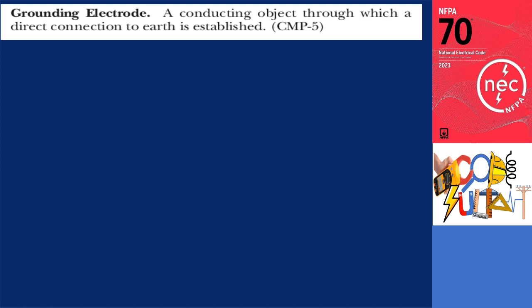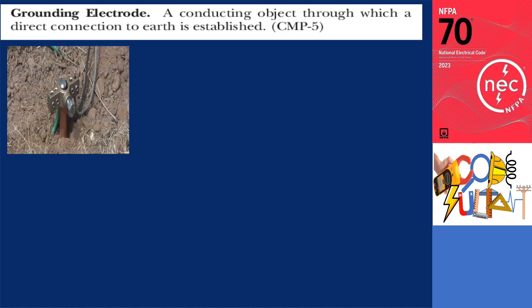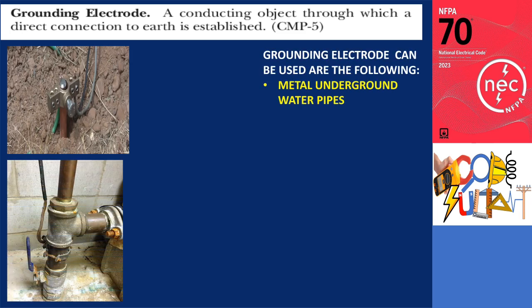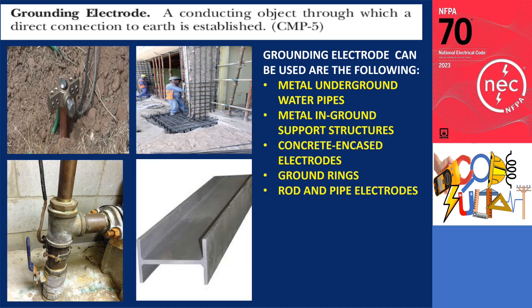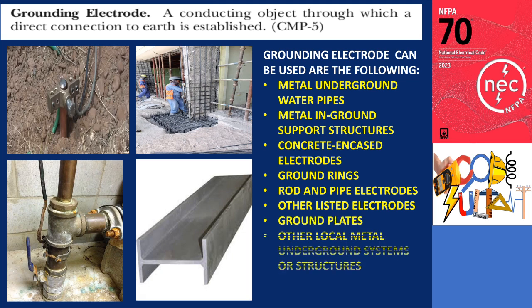What exactly is a grounding electrode? A grounding electrode is a conductive object that establishes a direct connection to the Earth. In the photo displayed, you can see a typical grounding electrode installation. Section 250.52 of the NEC outlines a list of items that can serve as grounding electrodes, including metal underground water pipes, metal in-ground support structures, concrete encased electrodes, ground rings, rod and pipe electrodes, other listed electrodes, ground plates, and other local metal underground systems or structures. These various grounding electrodes provide a reliable pathway for electrical current to flow into the ground, ensuring the effectiveness of the grounding system.